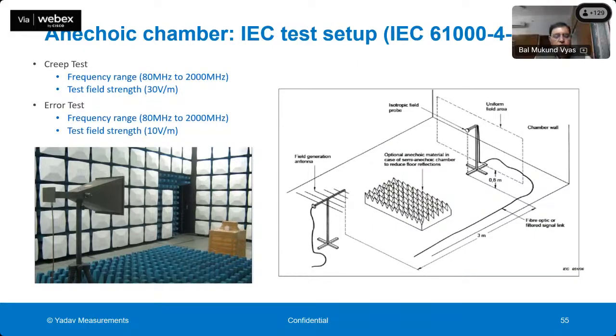To test the immunity of the meter against this kind of radio frequency field, which can be from 80 megahertz to a few gigahertz, you might have to test up to 6 gigahertz. The Wi-Fi which we are using in our houses nowadays is working at somewhere around 5 gigahertz. The Bluetooth works at 2.4 gigahertz. The mobile phones typically work at around 1000 megahertz, or sometimes even up to 1800 megahertz. So the air around us is full of all frequencies of radio frequency field, and this field can be in the range of 30 volts per meter.